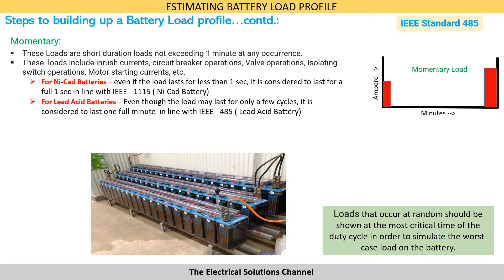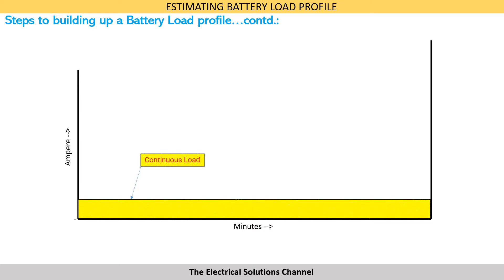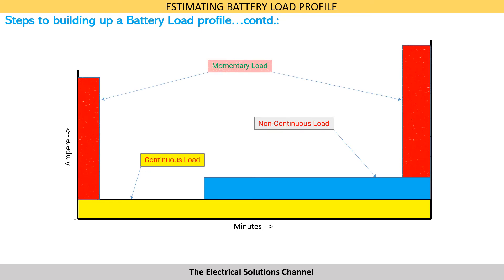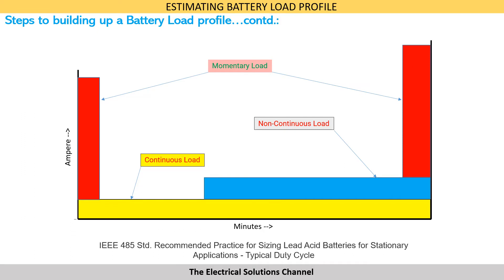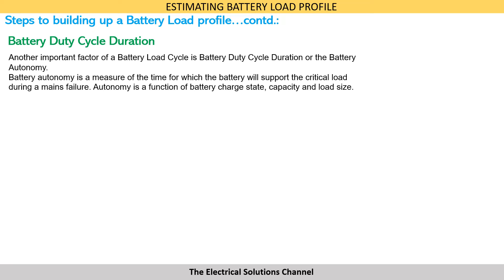Once the continuous, non-continuous, and momentary loads of a project have been estimated, combining all three gives us the battery load profile for that project. Another important factor of a battery load cycle is the battery duty cycle duration, or battery autonomy. Battery autonomy is a measure of the time for which the battery will support the critical loads during a mains failure, and is a function of the battery charge state, its capacity, and the load size.